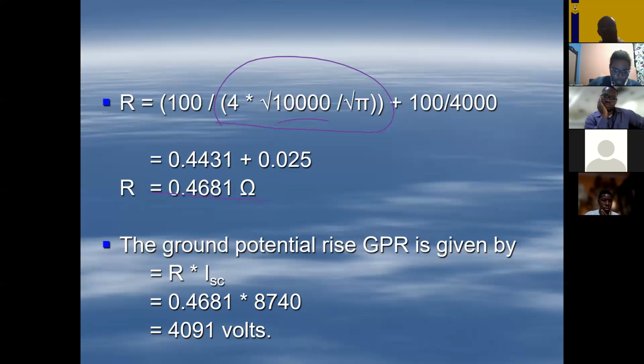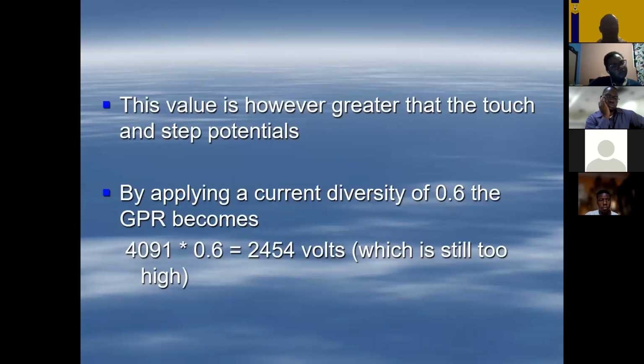So we apply some factors to this. The current diversity that we have here is quite similar to the diversity factor that we'd apply in your installation, where you assume not all the load will be on at the same time. So there will not be equal distribution across the mat - that's what you're hoping. Applying that type of principle, we get that 60% GPR, we go out to 2,454.